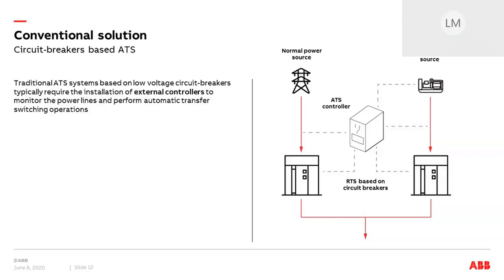Service continuity is playing an increasing role in low-voltage electrical installations, and automatic transfer logics are more and more demanded. Circuit breaker-based ATS solutions are typically used in the main distribution board, where low-voltage circuit breakers are installed as incomers for protection of the main busbar system. Low-voltage circuit breakers and their switch disconnector versions are typically installed with an external controller, like the ABB ATS021 and ATS022, to carry out automatic transfer switching operations.